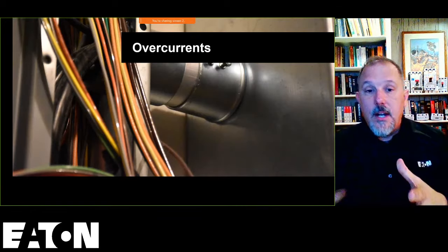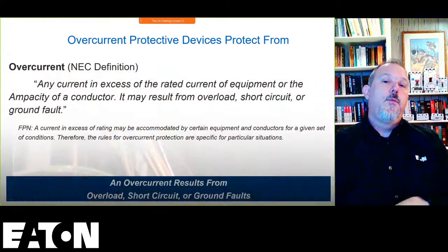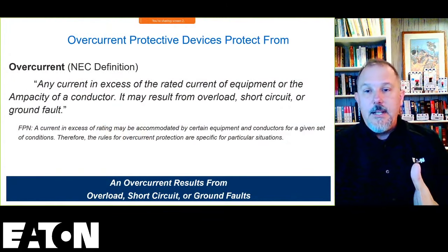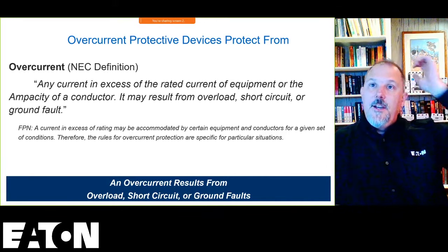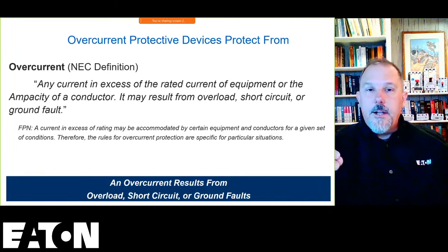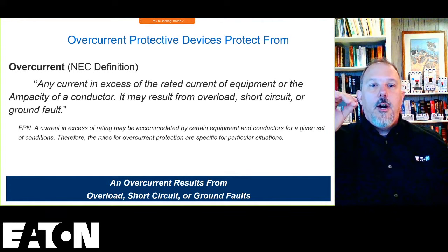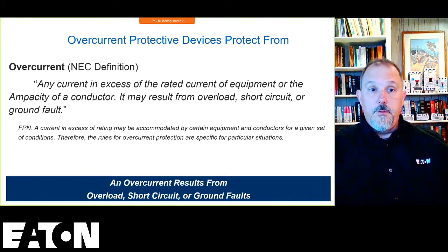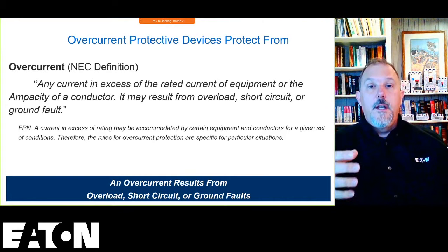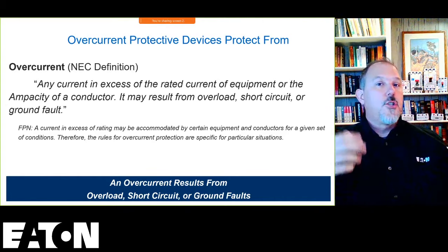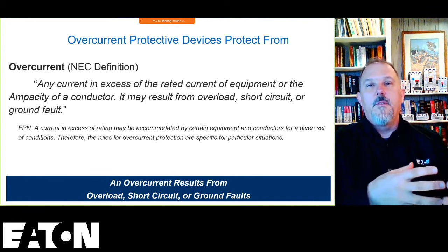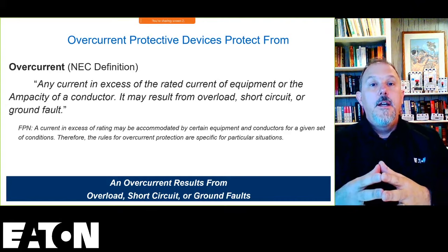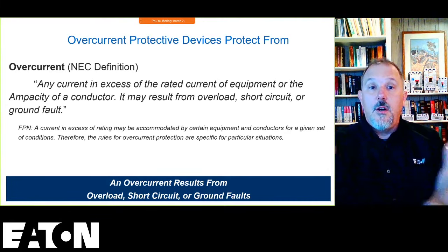All right, so let's now talk a little bit about overcurrents. What is an overcurrent? Why would I see overcurrents? What am I protecting from? An overcurrent is a generic term. Overloads, short circuits, and ground faults are all overcurrents. An overload is an overcurrent, a short circuit is an overcurrent, and what the NEC tells us is we have to provide overcurrent protection, which incorporates all of those.